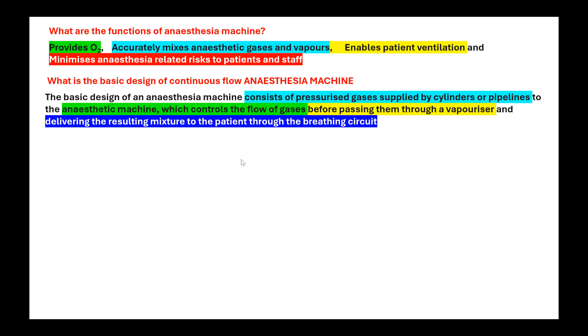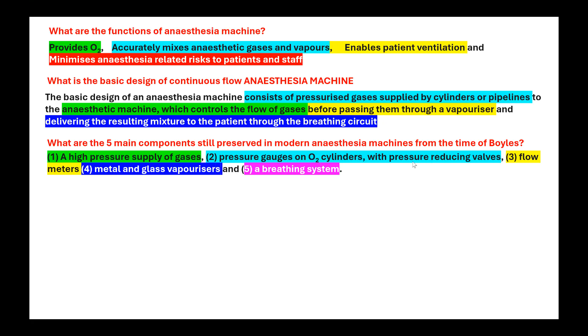Now, what are the five main components still preserved in modern anesthesia machine from the time of Boyle's? So, based on the same question, you have a high pressure supply gases. There is a pressure gauge of oxygen and nitrous oxide or other cylinders or pressure reducing valve. Then there is flow meter, which you have even in your latest modern workstation also. Without flow meter, you cannot deliver gases. Then there are metal and glass vaporizers and breathing system. Here I told you about the four components. The fifth component added here is the pressure gauge and the pressure reducing valves.